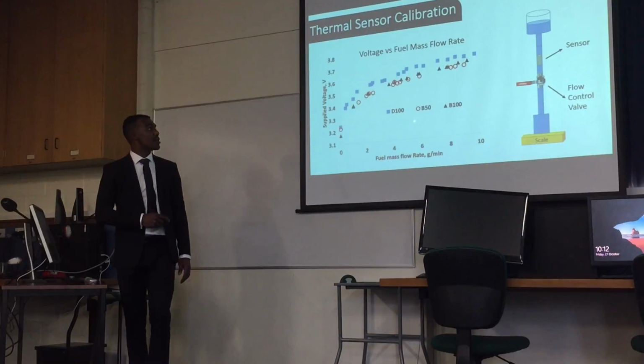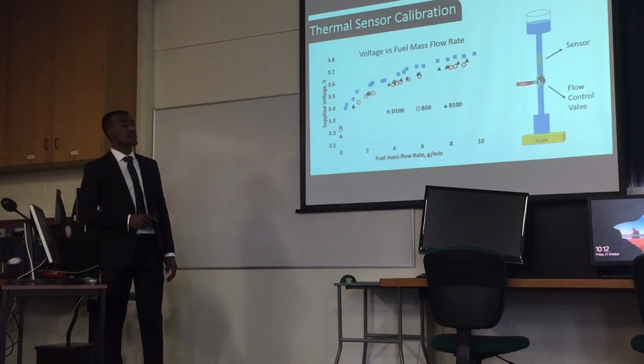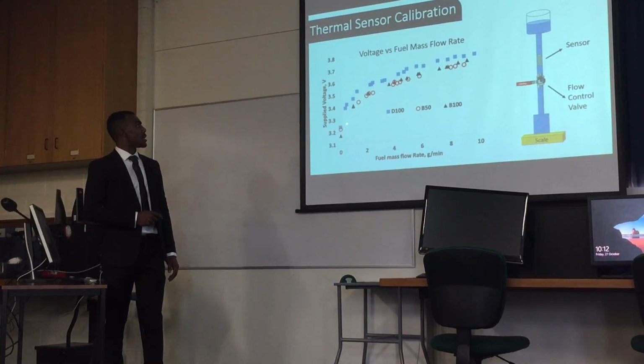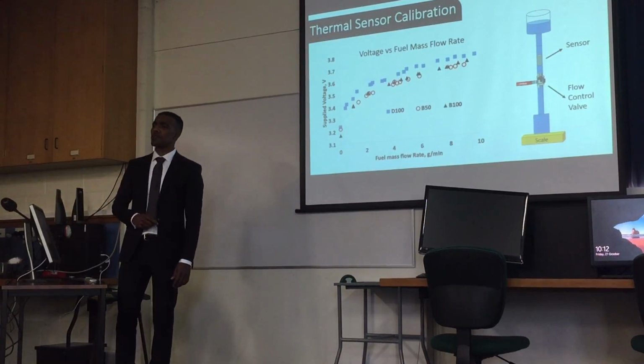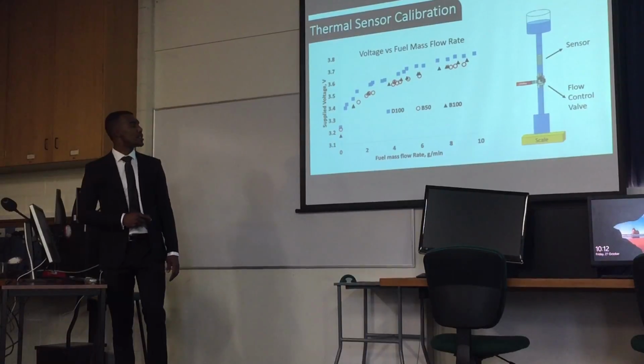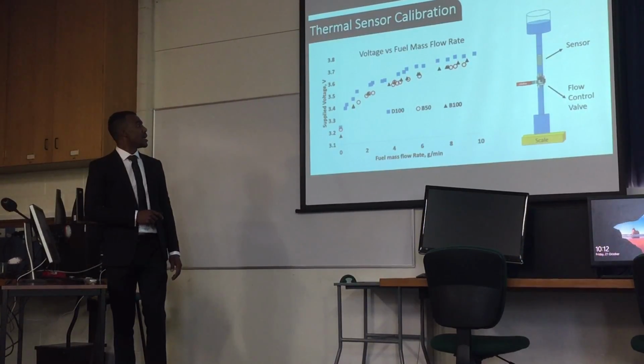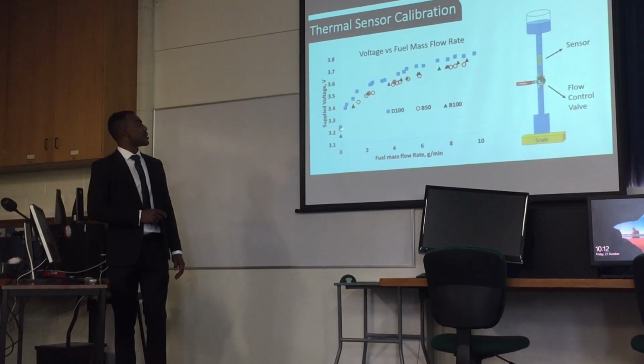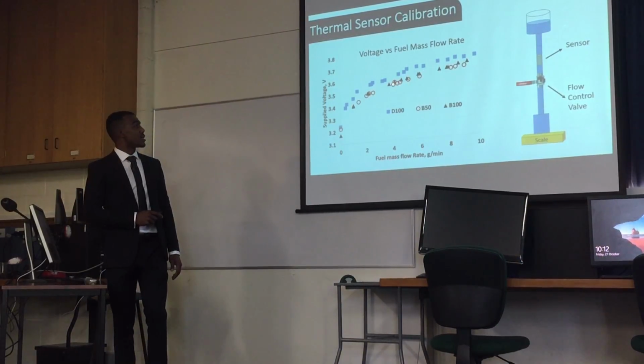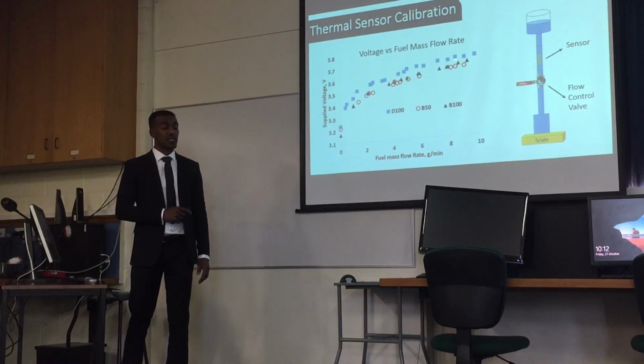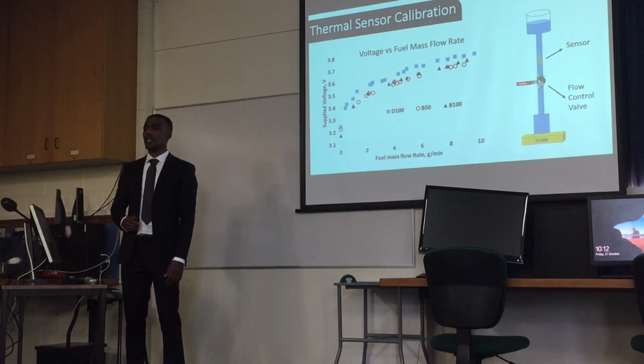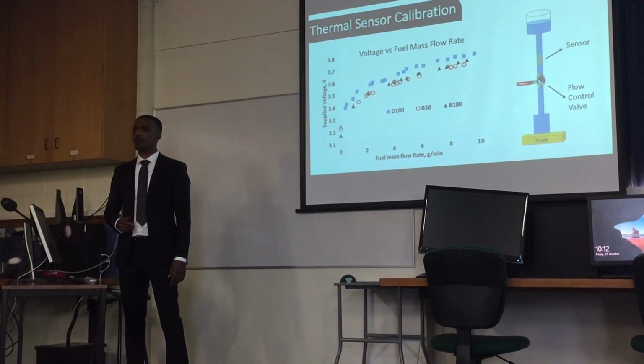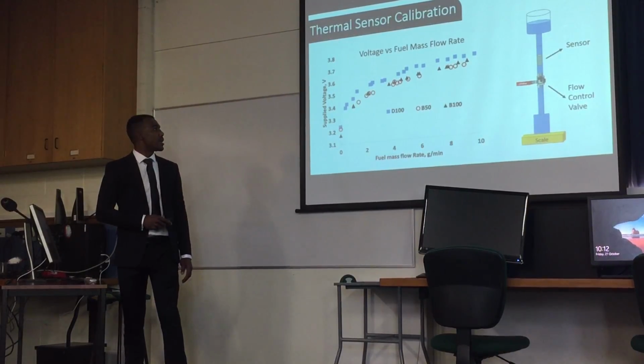We did the calibration on D100 diesel, on a 50% biodiesel, 50% diesel blend, and also on neat biodiesel at 100%. You see the curves look very good, with the same trend. The biodiesel and the blend readings are lower than the diesel, and that's due to differences in the thermal properties of the fuels.